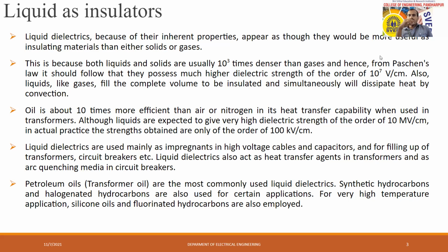Liquid dielectrics are mainly preferred for high voltage cables and capacitors. Whenever we fill up transformers or circuit breakers, liquid dielectrics act as a transfer agent in a transformer, and also as an arc quenching medium in circuit breakers.